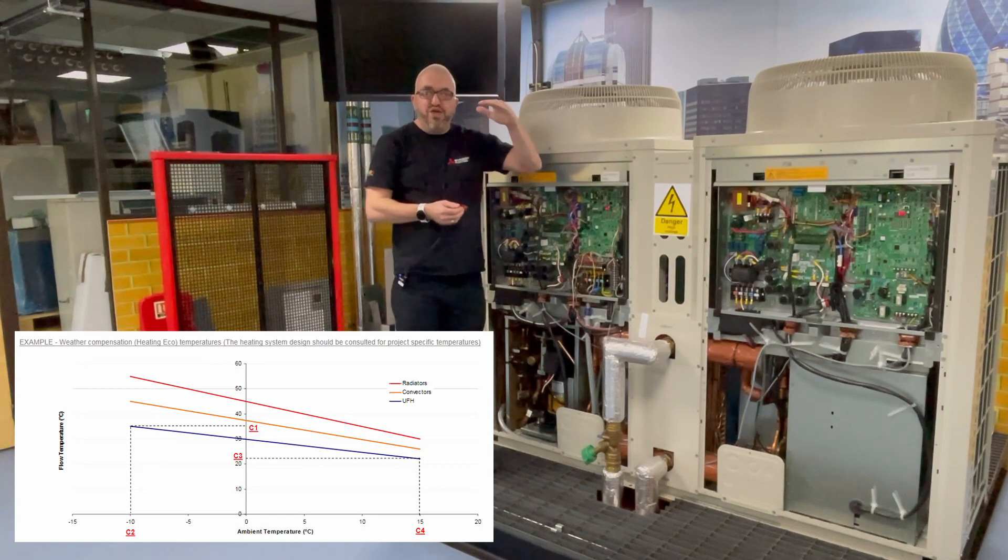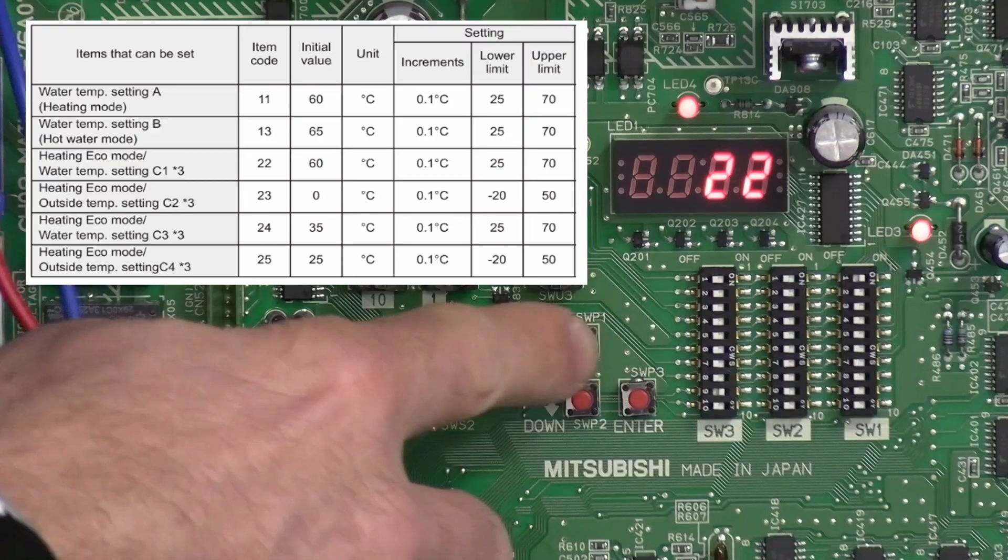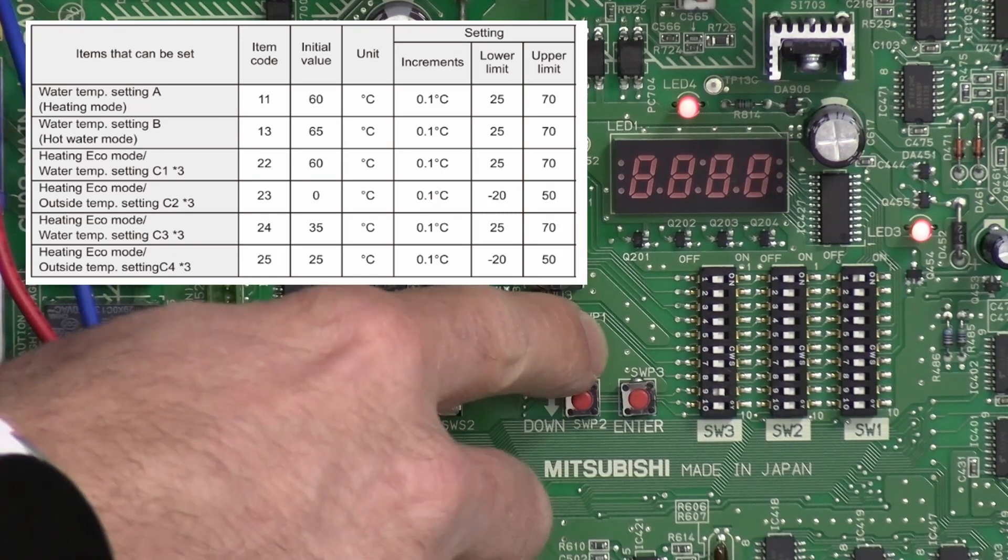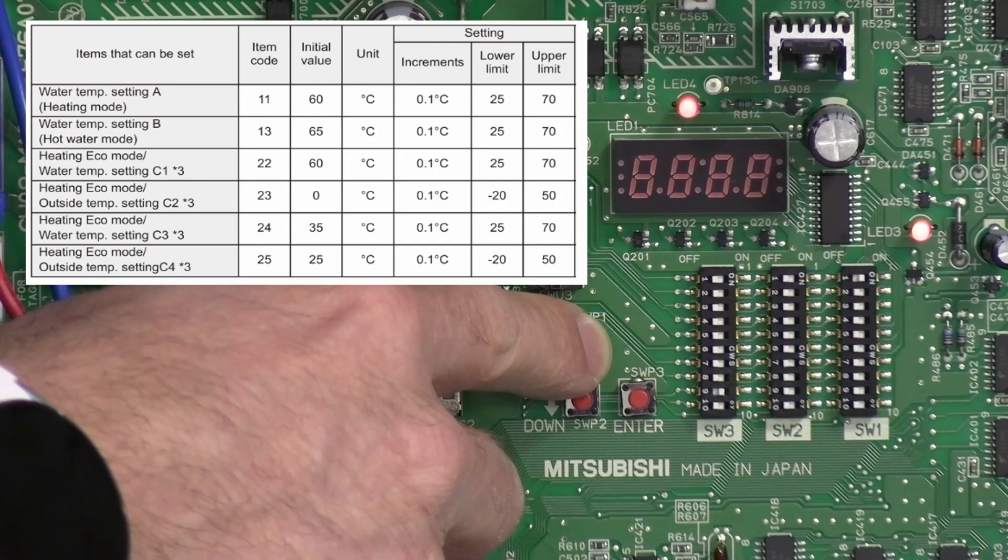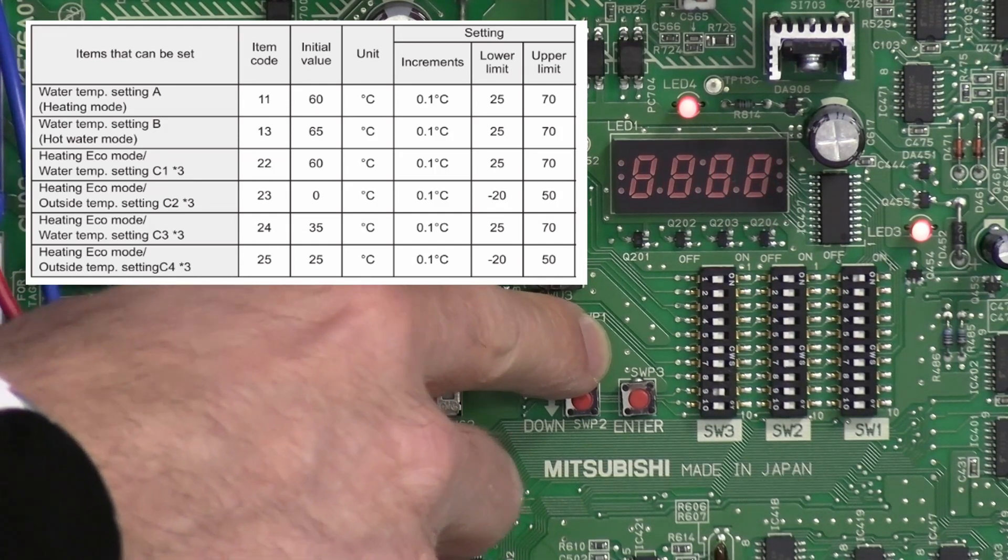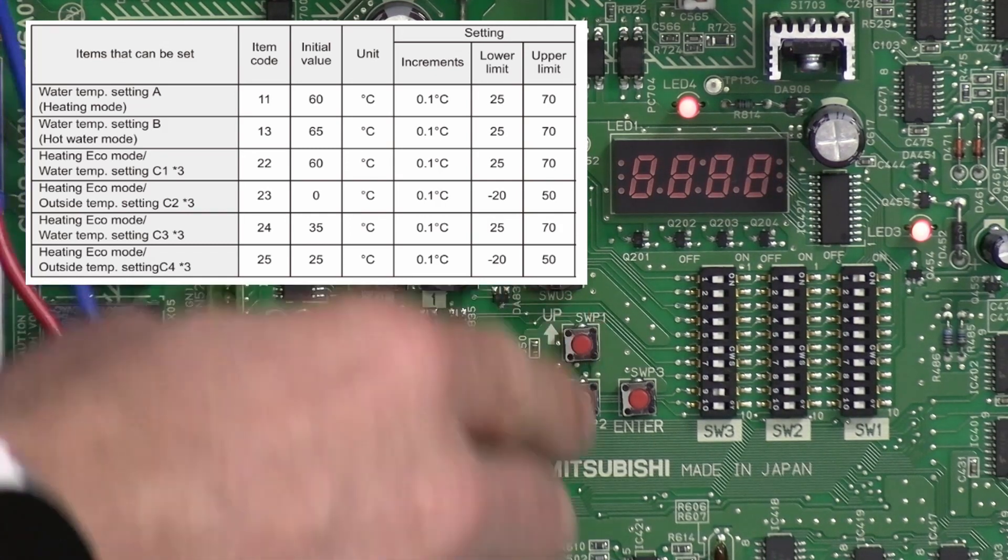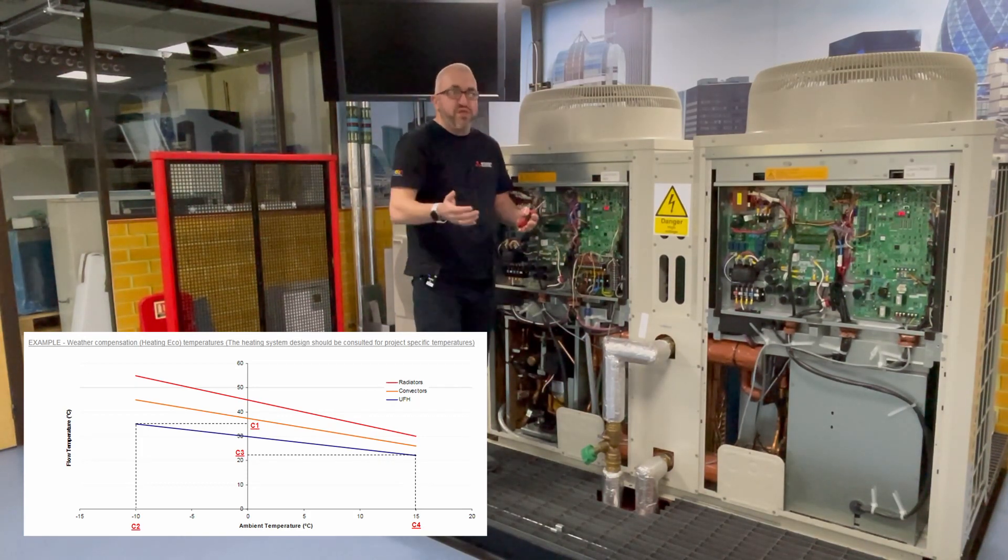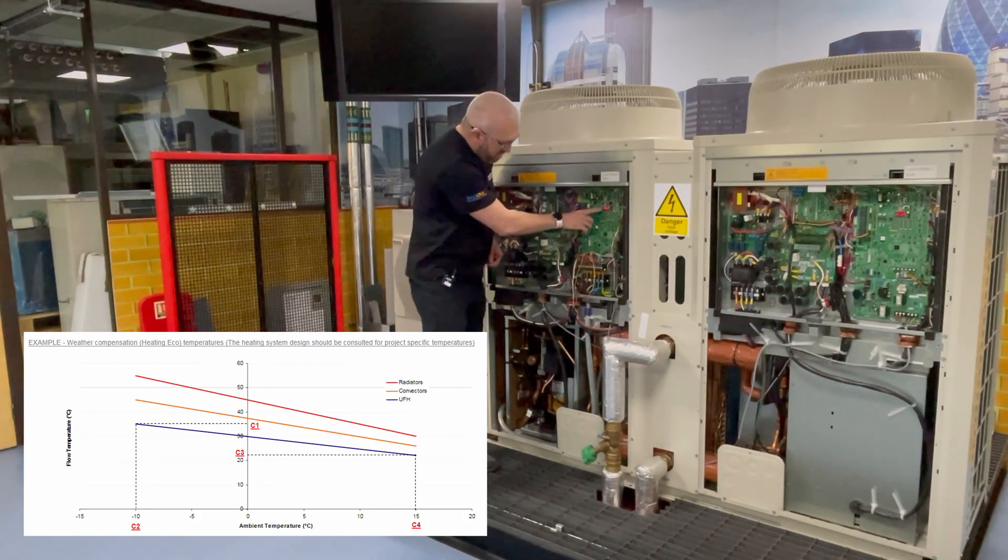So item 22, let's press the up button and it's currently set to 60 degrees. Let's increase that up, let's bump that up to say 65. Obviously these target temperatures will be in line with your design or you consult the specification, whatever you're working to. It could well be to do with your heater emitters, so what temperature heater emitters have been sized to.